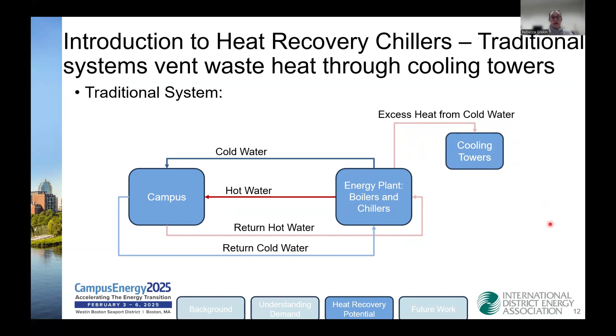energy plant. Basically, what happens then is the return cold water has excess heat because it's been heated up because the cooling has been used. And that excess heat is then exhausted through the cooling towers. So what that means is that you're wasting heat through the cooling towers. That wasted heat is not being used within the system. However, when you have a heat recovery chiller, they are more efficient because you can actually recycle that waste heat.